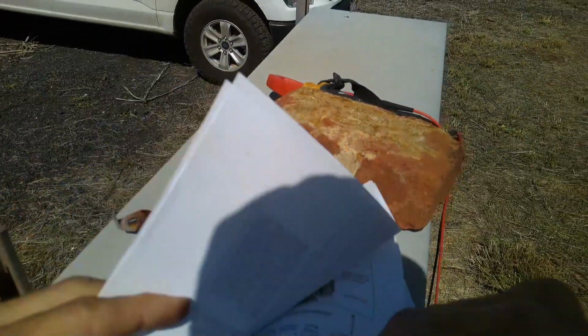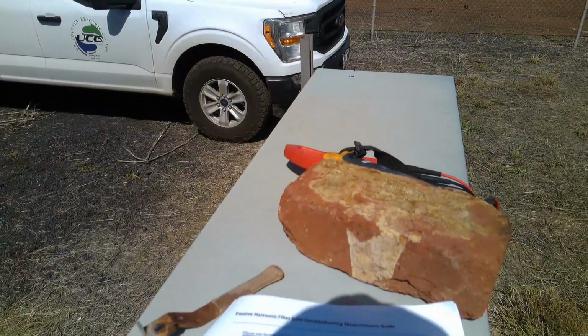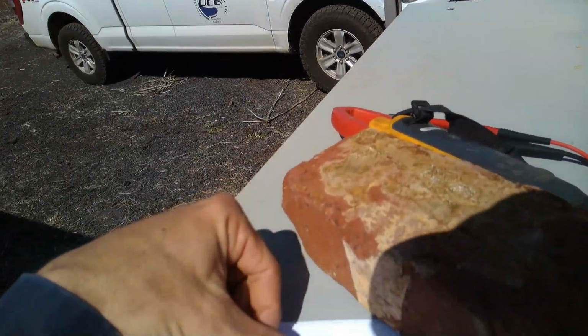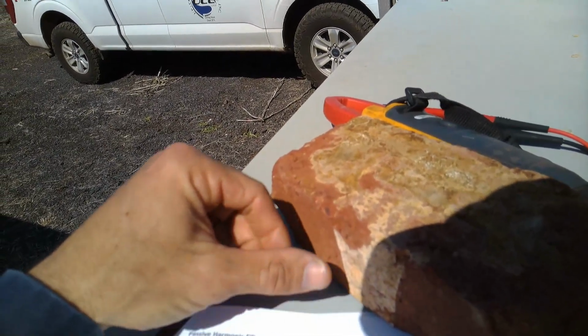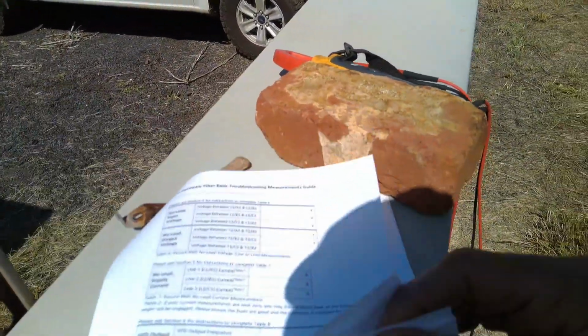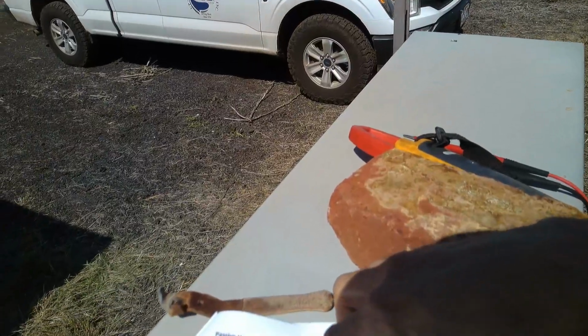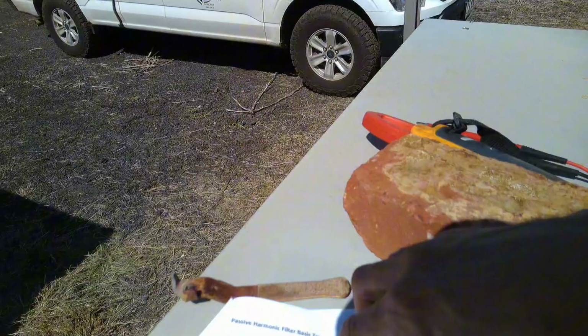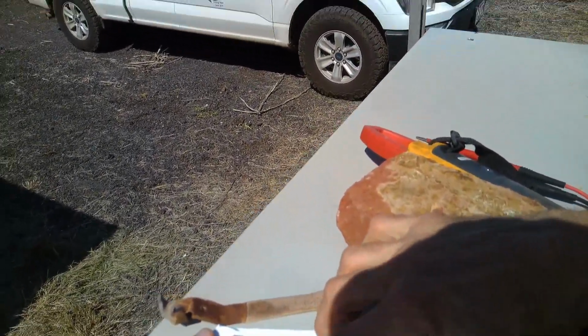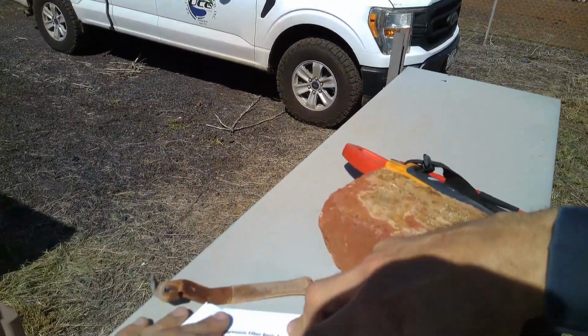They want me to take these measurements, section 5, input terminals and output terminals at the line reactor. So voltage between L1 and A1 and L2 and B1. Just verify that. Oh, L1, A1 is the same thing. Yeah, okay. So they want the voltage from L1 to L2, L2 to L3, L3 to L1. And then they want the no load voltage from T1 to T2, T2 to T3. Yeah. This calls for gloves.